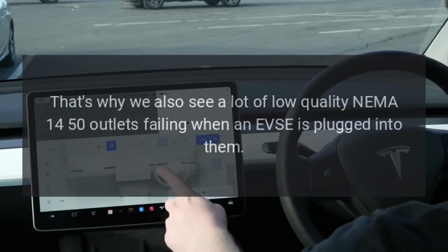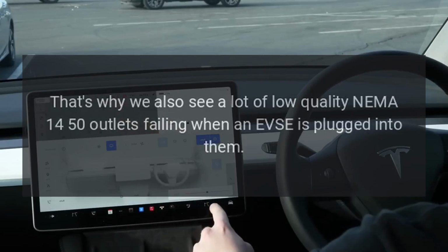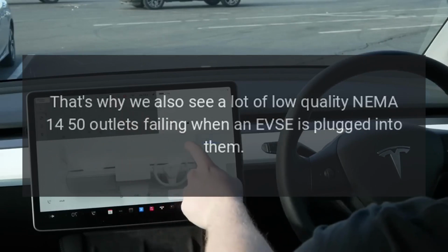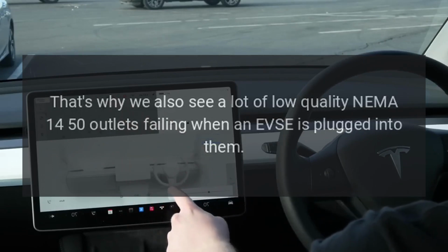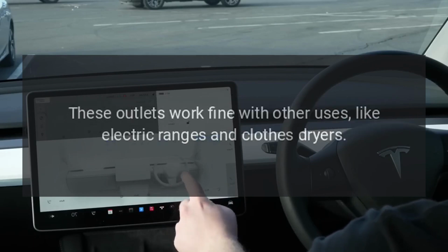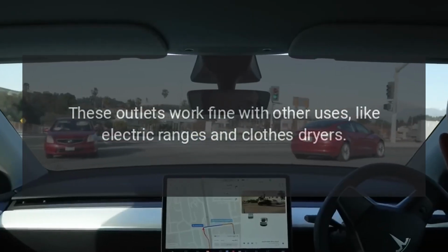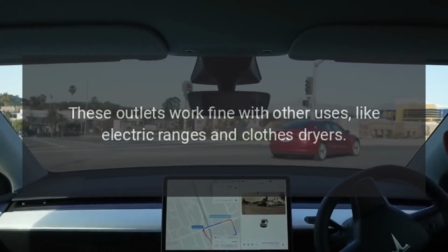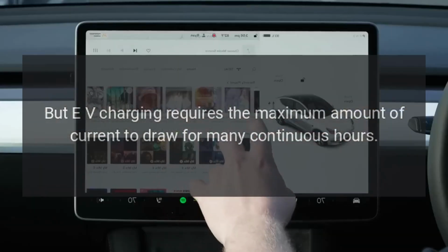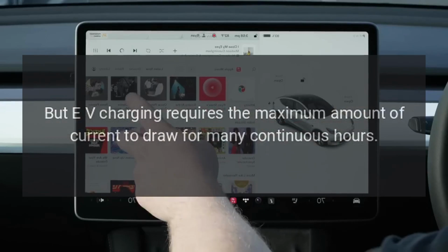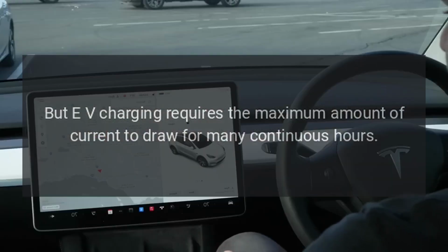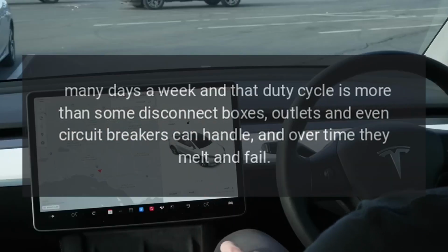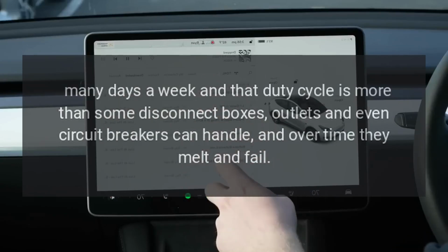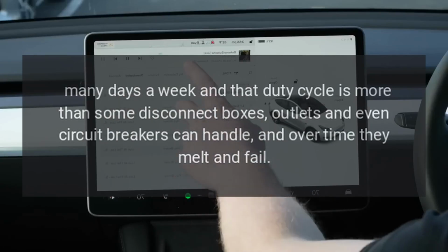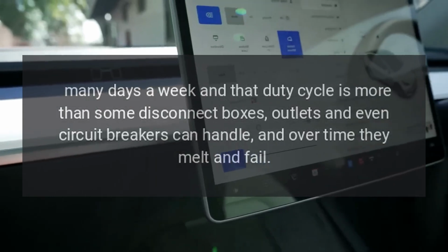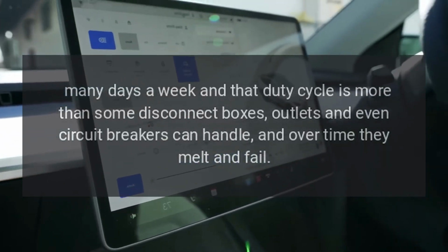That's why we also see a lot of low-quality NEMA 14-50 outlets failing when an EVSE is plugged into them. These outlets work fine with other uses, like electric ranges and clothes dryers. But EV charging requires the maximum amount of current to draw for many continuous hours, many days a week, and that duty cycle is more than some disconnect boxes, outlets, and even circuit breakers can handle, and over time they melt and fail.